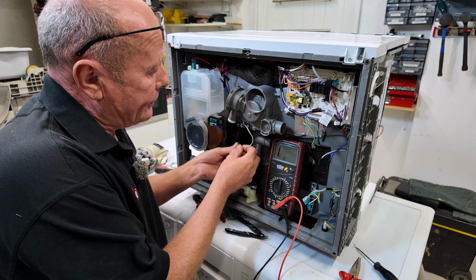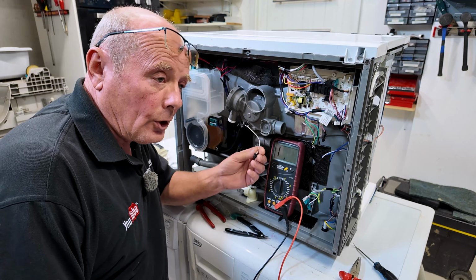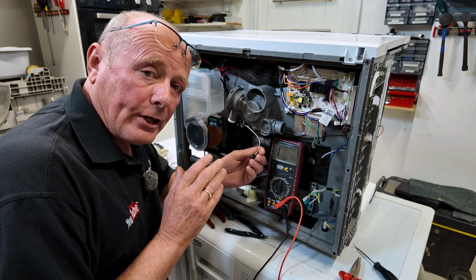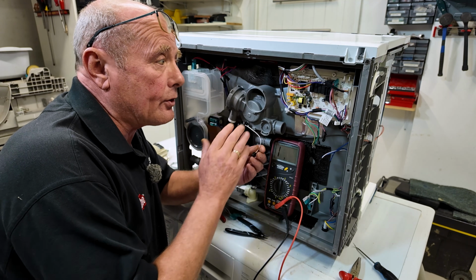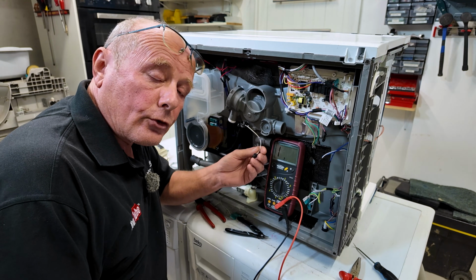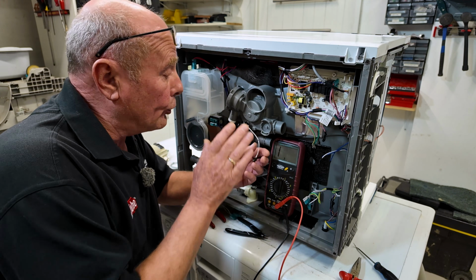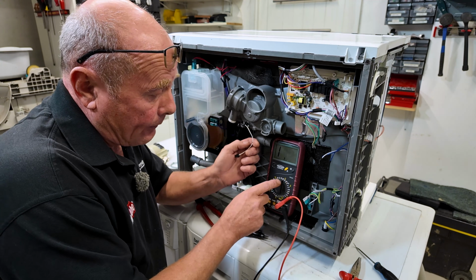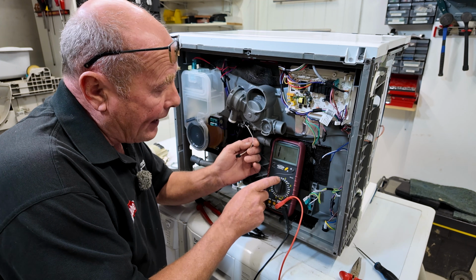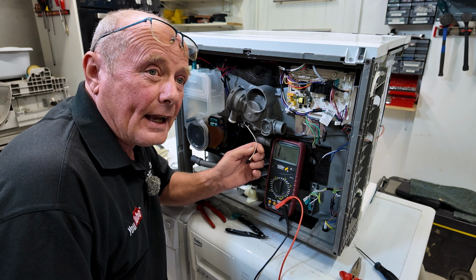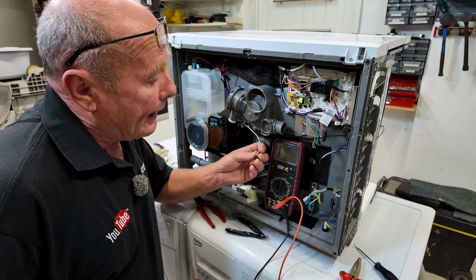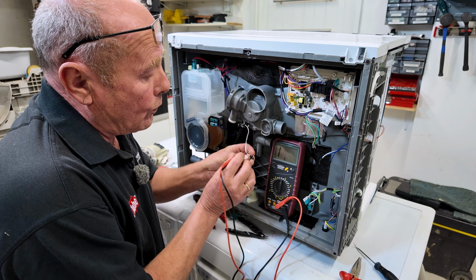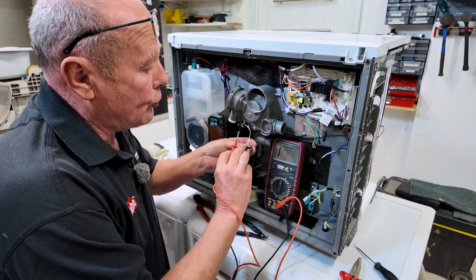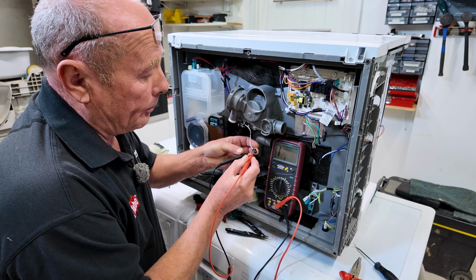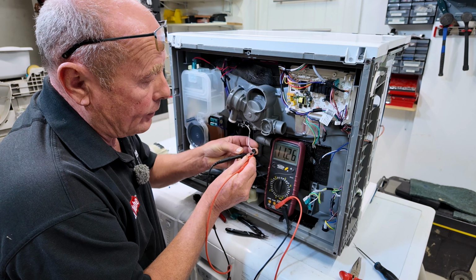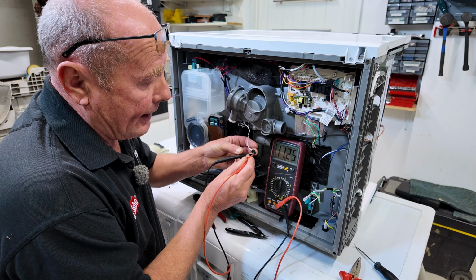What annoys me nowadays, especially with NTC sensors which have a value at certain temperatures that changes as temperature changes, giving information to the circuit board, is that a lot of manufacturers don't give you the correct data to know whether the NTC sensor is good. I've set my meter to 20K. Room temperature here is about 24-25 degrees, and I'll take a quick reading so you know what your NTC sensor should read at this room temperature. It may help others in future - our NTC value is 1125.